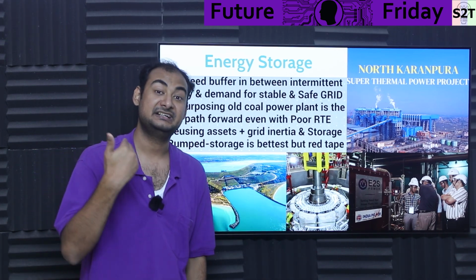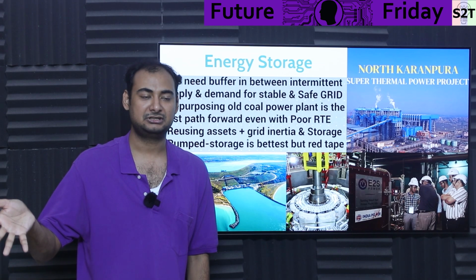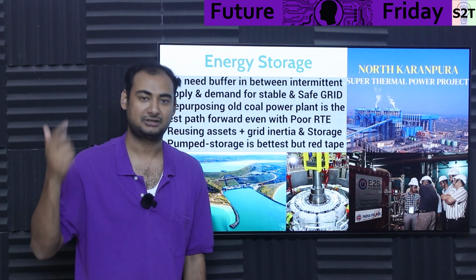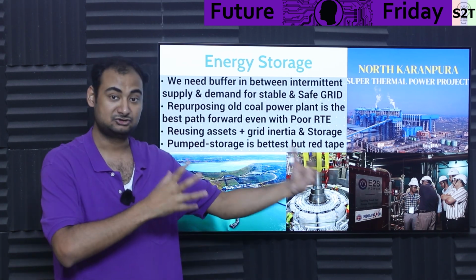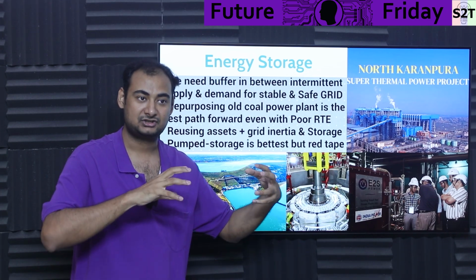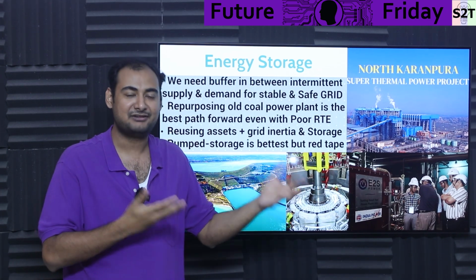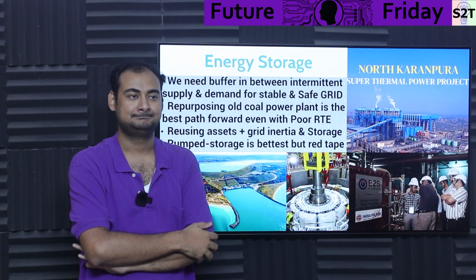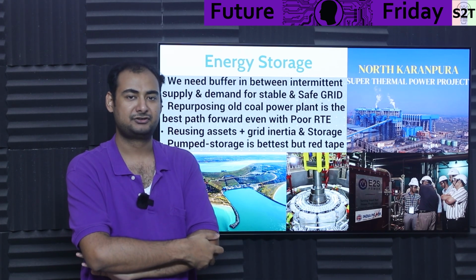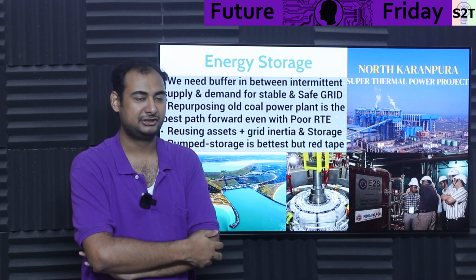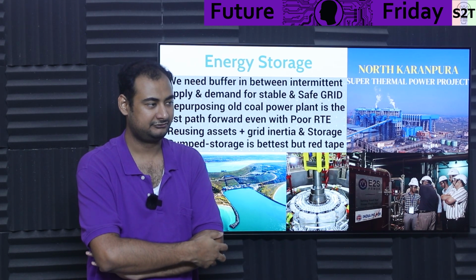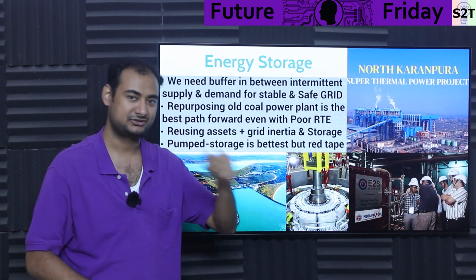And the same happens in reverse. You melt your metal, so to say, and you turn it off. Boom, 10 megawatt gone. Now so much steam, so much spinning power, it tries to spin faster. But here's the deal, you still have hundreds of tons of inertia. That 1500 RPM becomes like 1501, 1505, 1510. Okay, red alert, okay, cut down steam.